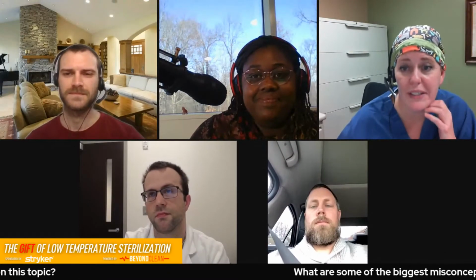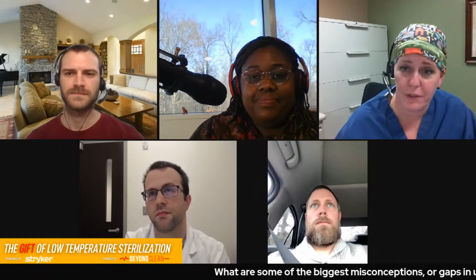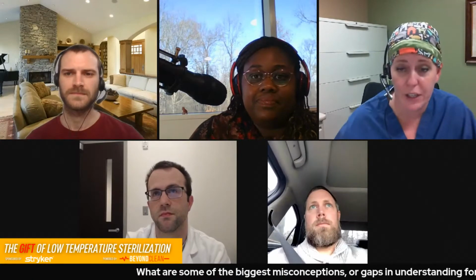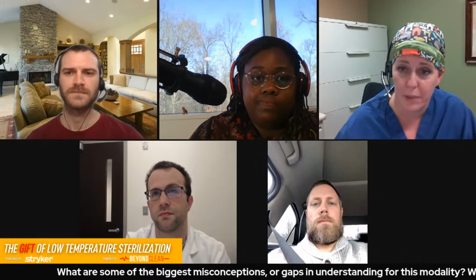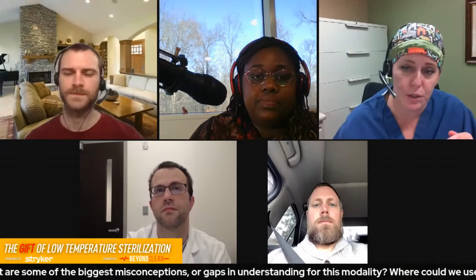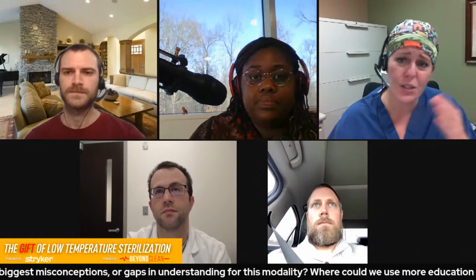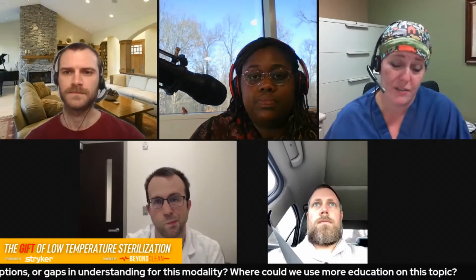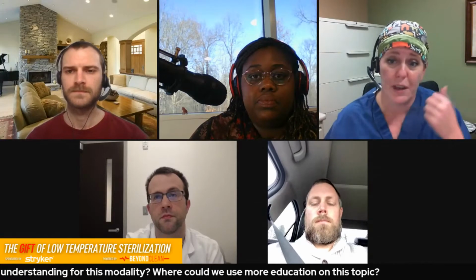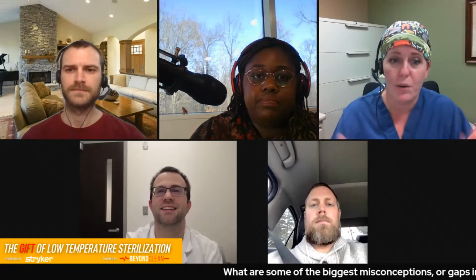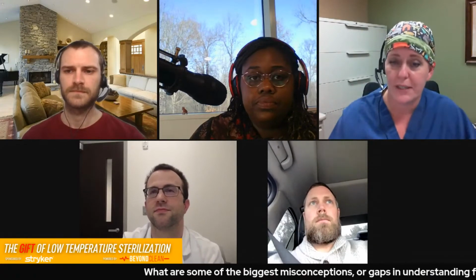Yeah. I would say there are some other options. So like if you have a different brand that's not listed in the IFU, a different manufacturer, that manufacturer might have its own validation or compatibility matrix. Right. You can also look at, and it's always a mix, and it's always a judgment call, if, in my opinion, if we're going to be honest, because you have the chemical, you have the machine, you have the device. You always have to line them up. Very rarely are they like, oh, we planned all of this together between all of us. So it's always this decision-making tree, basically.